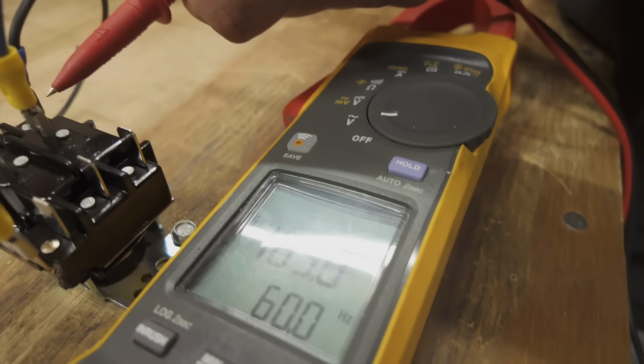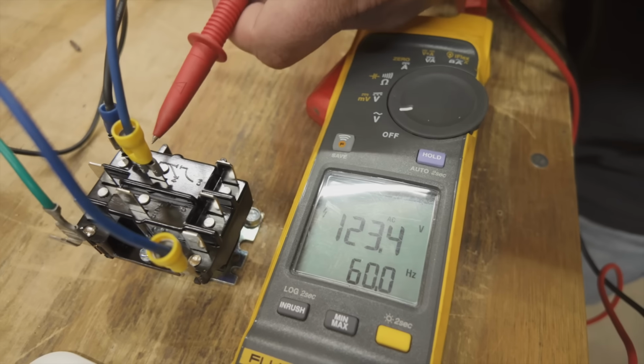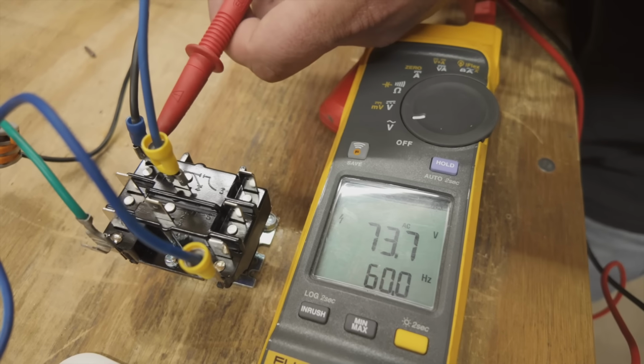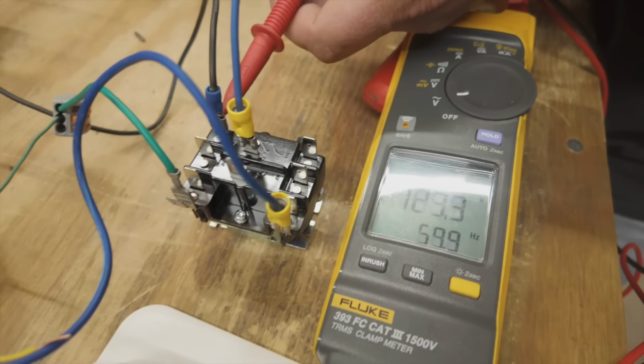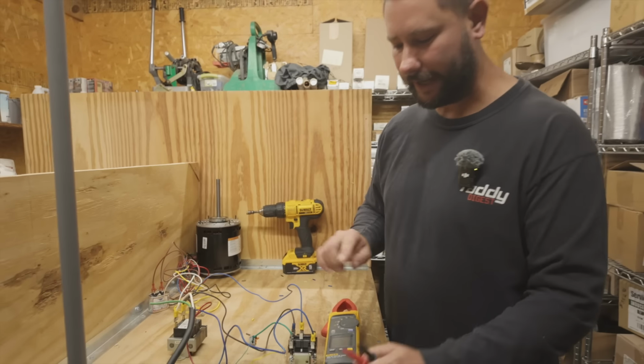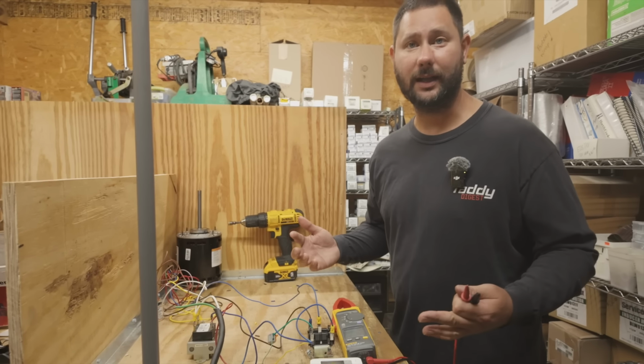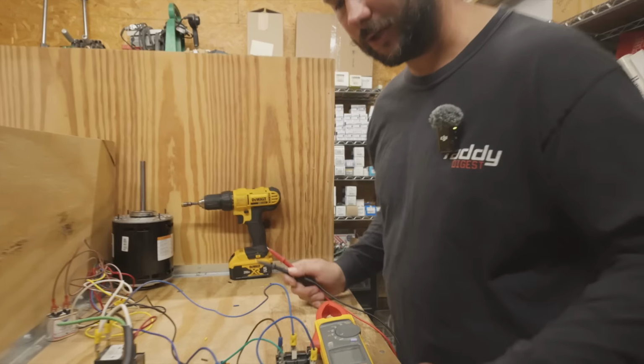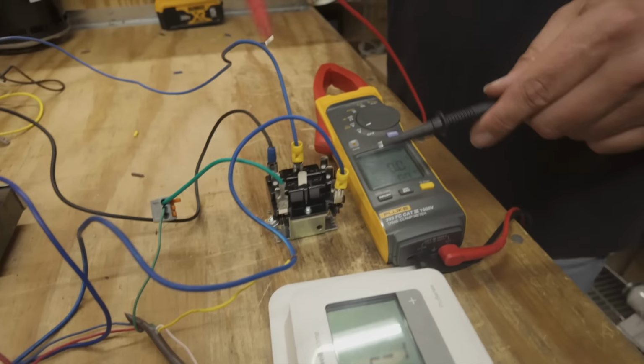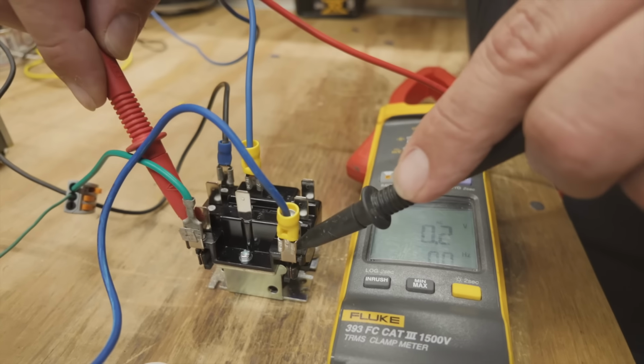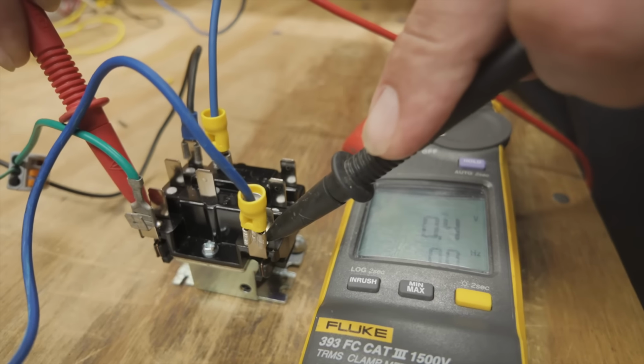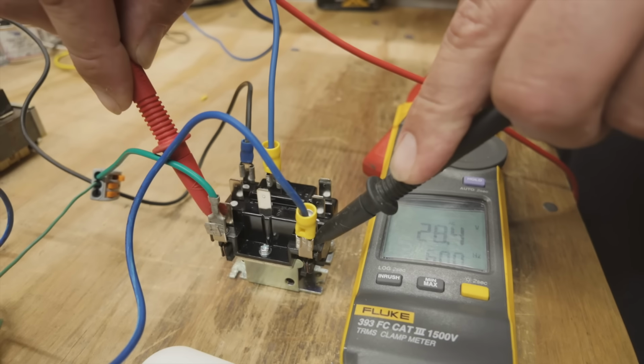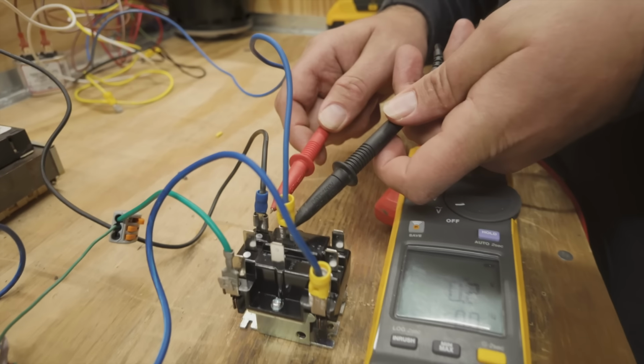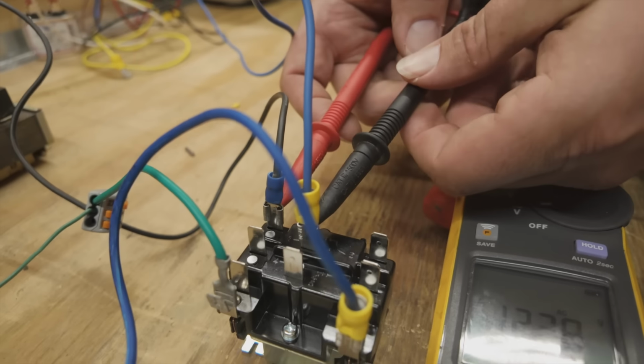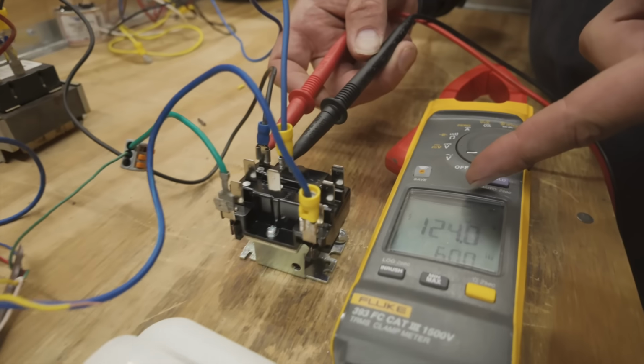And then if I check with my meter, again, from here to here, I got voltage, right? And then if I go to here, look. So we got voltage going all the way through. See? See how I did that? We got voltage going all the way through. Why? Because we have a normally closed contact. Put it back on. Now watch what happens when I turn the fan to on and I send 24 volts to this coil. We sent voltage to the coil, the normally closed contact has now opened.